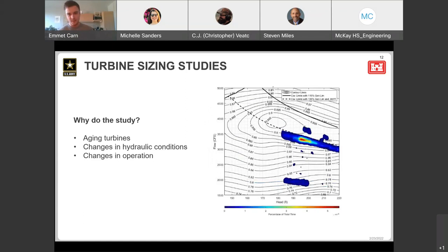Maybe we can uprate the units and get more power out of them if there's availability of flow, and that translates to changes in operation over time. You can see this diagram - it was a dam I was studying, and this is what we call a heat map. On the x-axis is head, which is the elevation difference at either side of the dam, and on the y-axis is flow through the unit. We can pinpoint the type of operation the unit experiences, and with those different amounts of flow or elevations, we can pinpoint what efficiency the unit is operating at.